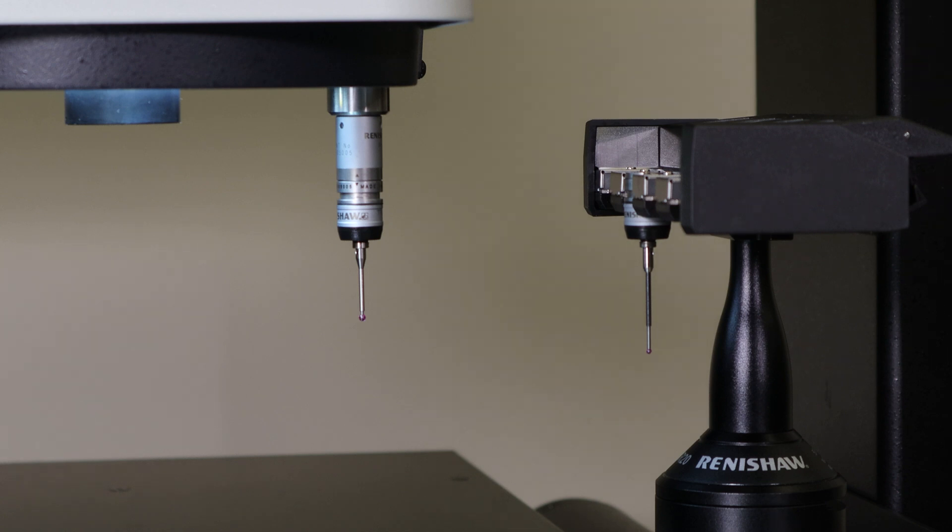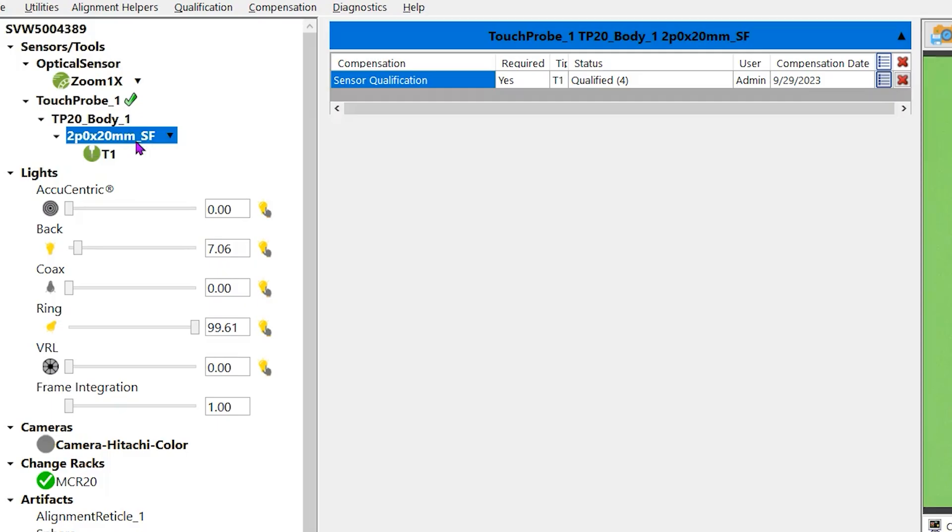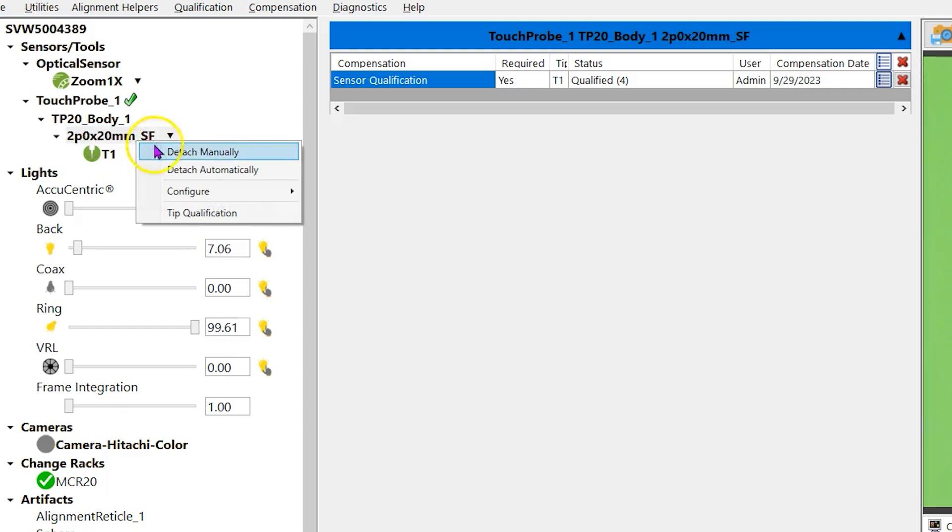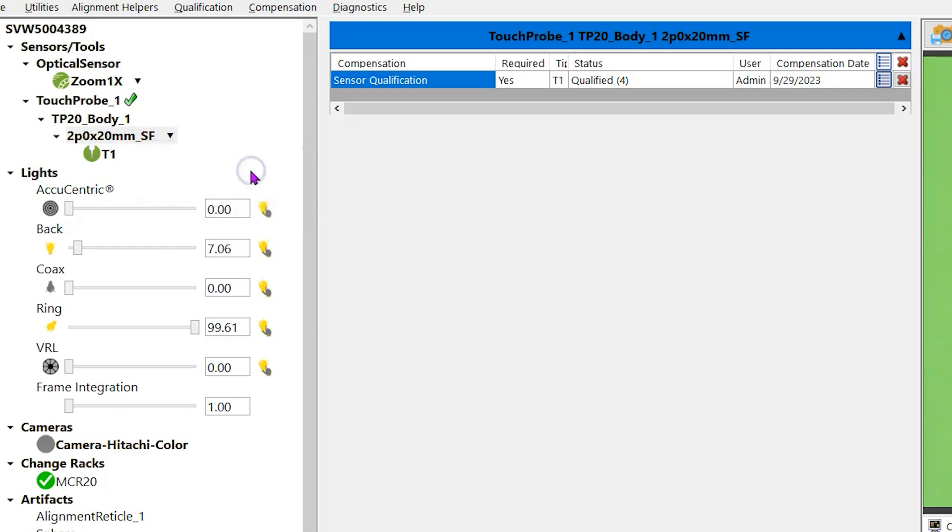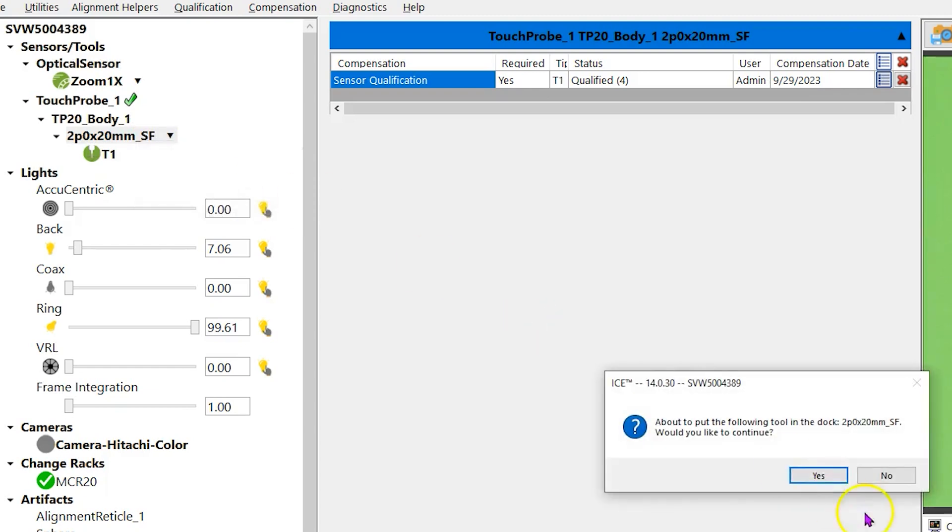To dock the probe, left mouse click on the probe name, then right mouse click and choose detach automatically at the pop-up window. A window appears letting you know the machine will dock the probe.